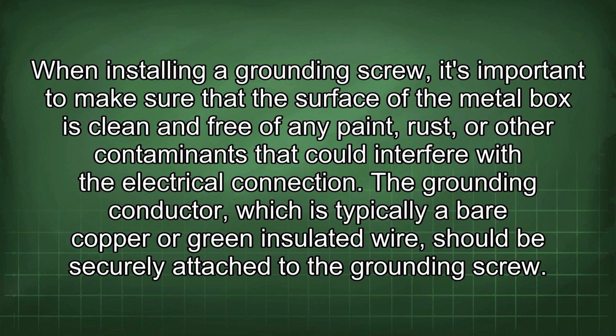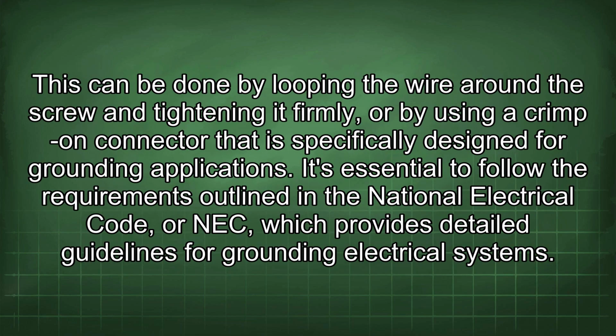When installing a grounding screw, it's important to make sure that the surface of the metal box is clean and free of any paint, rust, or other contaminants that could interfere with the electrical connection. The grounding conductor, which is typically a bare copper or green insulated wire, should be securely attached to the grounding screw. This can be done by looping the wire around the screw and tightening it firmly, or by using a crimp-on connector that is specifically designed for grounding applications.